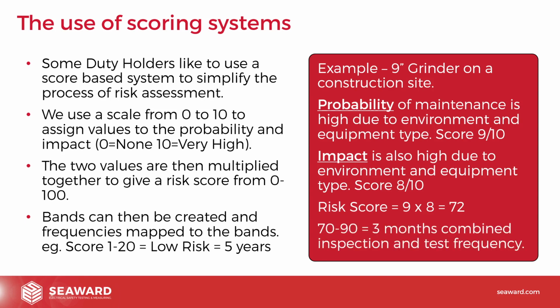And if our policy said that we put it into bands and we said, right, 72, if it's between 70 and 90, then it needs testing every 3 months with a combined inspection and test. So you can imagine how a duty holder could actually set up a system and then just go through, make these judgments, and actually document why they've done these things, how it all fits together, and actually come up with a score-based or risk-based system. It's one way of making it a bit less subjective and adding a bit more structure into it, really, from that side of things.